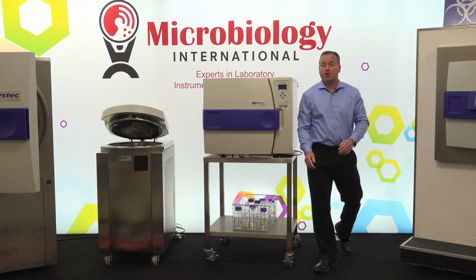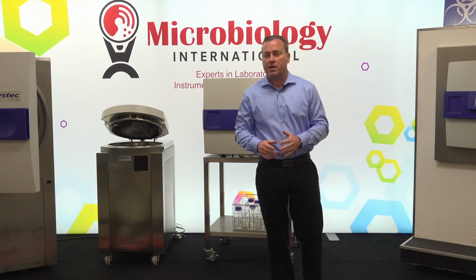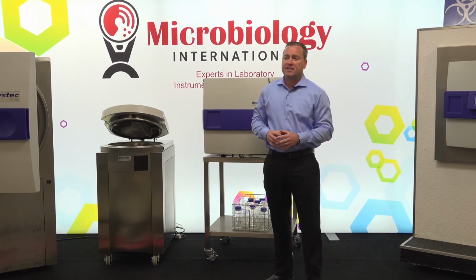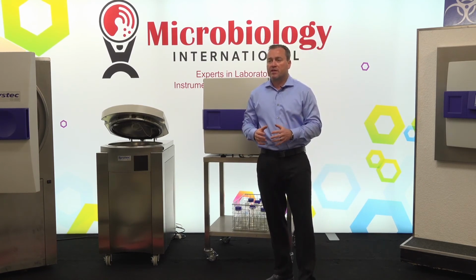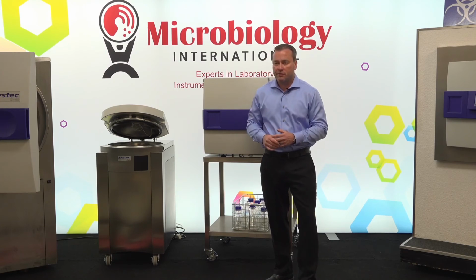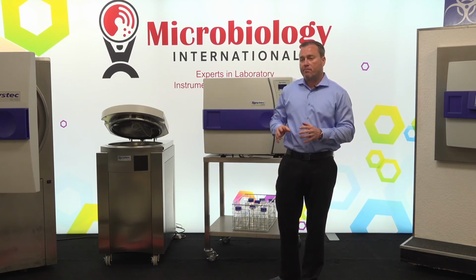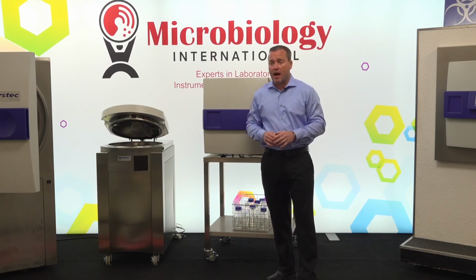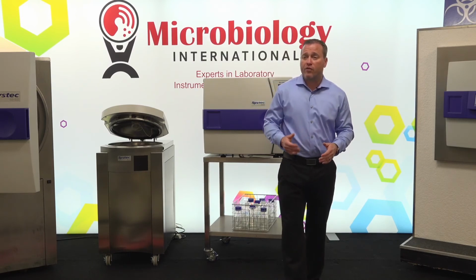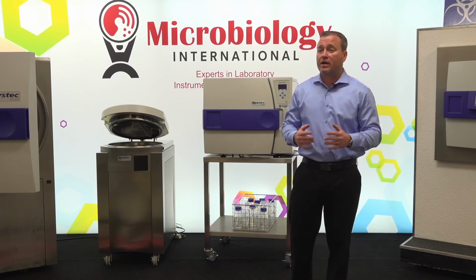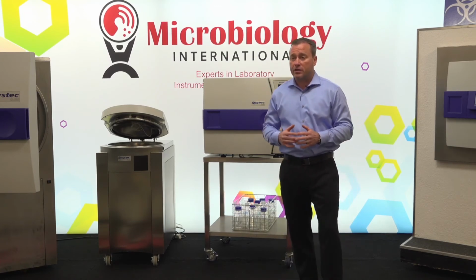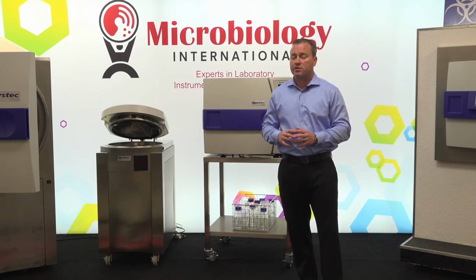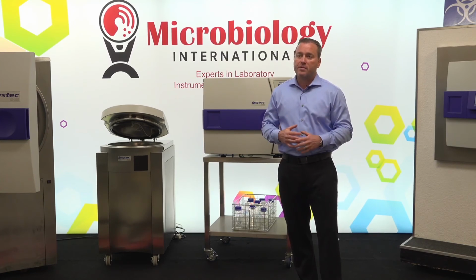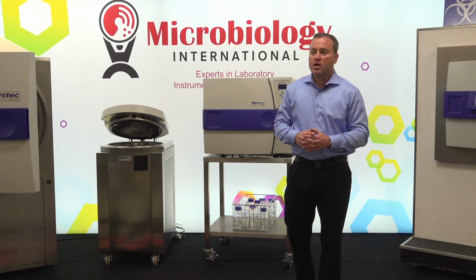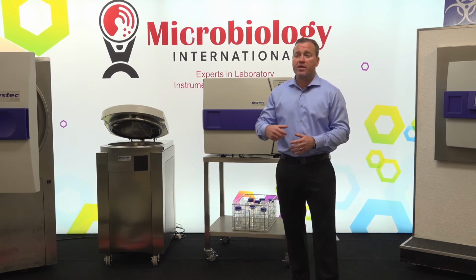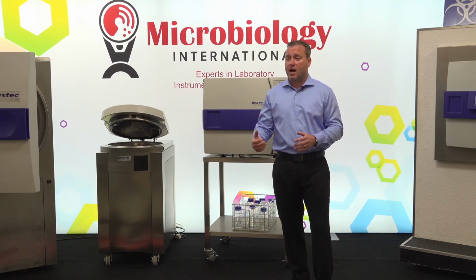We do. So our service team offers complete IQ, OQ, and PQ services. The IQ, OQ is a standard package that would be for the installation and operational qualification of the system. We do tailor-make PQ services depending upon your application. We do these quite often with pharma companies or with any companies that are doing glass testing that have a very specific requirement to meet for their different cycles. We write all of that documentation and work collaboratively with you to make sure we achieve exactly what you want to do, and then we'll do the performance qualification at the time of installation as well.